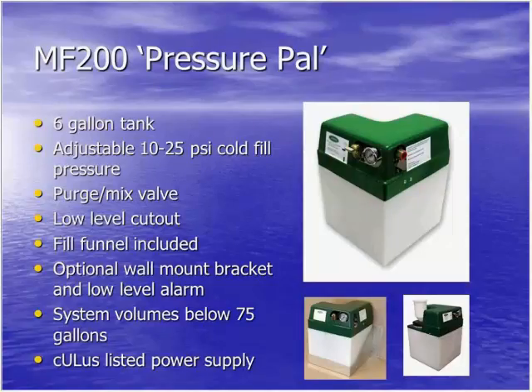There's also an optional wall mounting bracket and low level alarm. I should mention too, I was going to change the slide but didn't have time, that we do have an MF200-LPA version, and that's a low pressure alarm built into that particular unit. So let's say the unit was set for 18 psi, and for some reason you develop a leak, the pressure goes down, and there isn't enough fluid in the unit to maintain pressure.